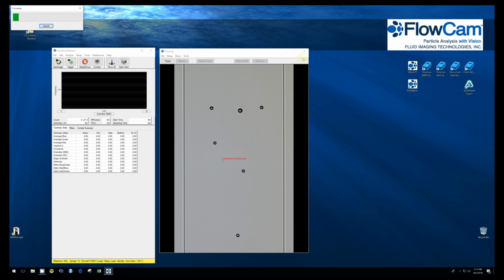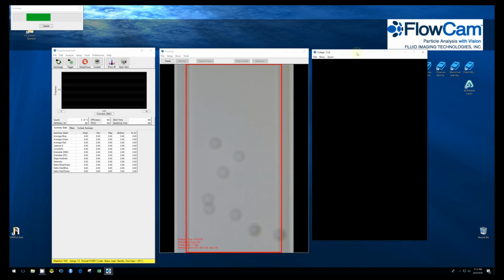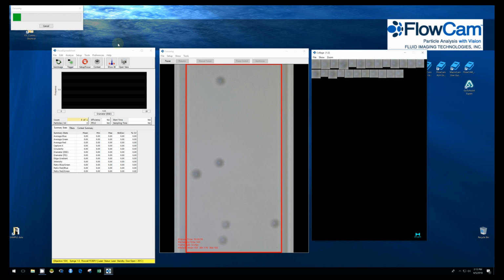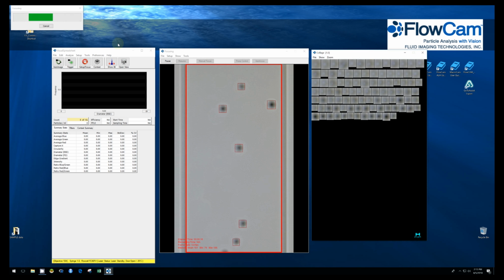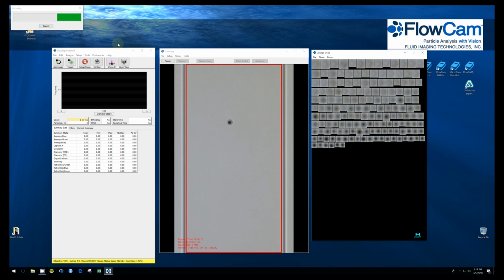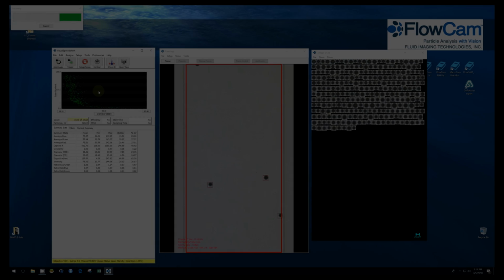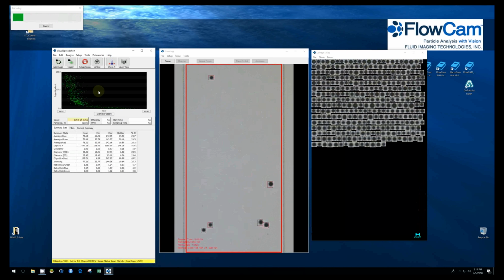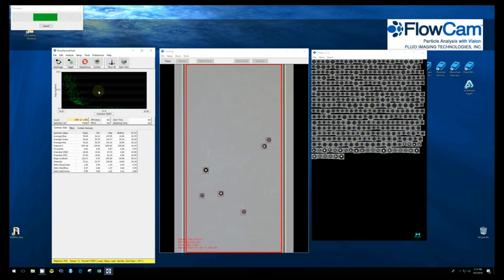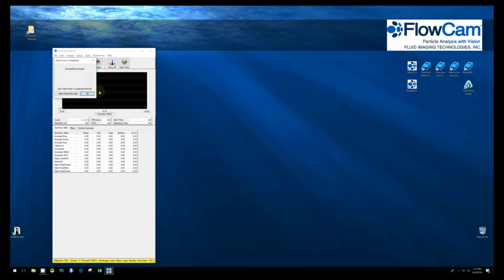As your focus beads are drawn through the flow cell, you will hear the stage moving and can view the beads within the focal plane. Do not bump the instrument or tamper with any software settings during the autofocus procedure. A status bar will show the progress as you view the camera capture. When the autofocus procedure is complete, a message dialog will appear that states either successfully focused or autofocus not successful.